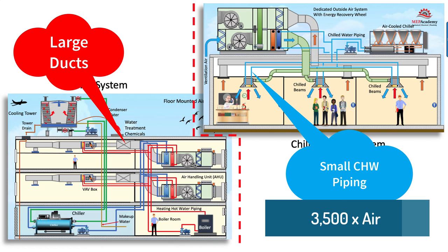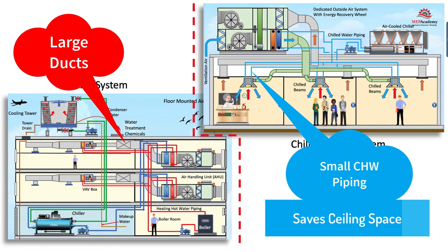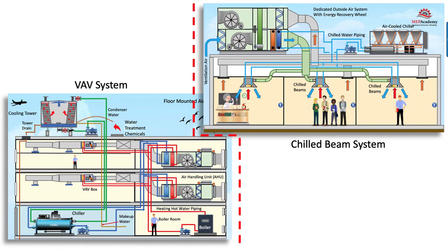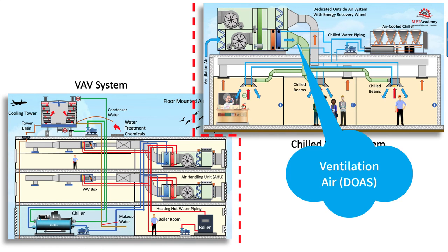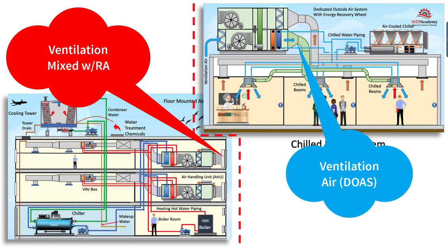This saves on ceiling space and allows for lower floor-to-floor heights or higher ceilings. The VAV system increases the volume of air to satisfy the space, while the chilled beam system increases the flow of chilled water. The ventilation air delivered using the chilled beam system is the proper amount based on space usage and occupancy level. With a VAV system, the volume of ventilation air is less precise, as ventilation air is mixed with return air before being delivered to the space.